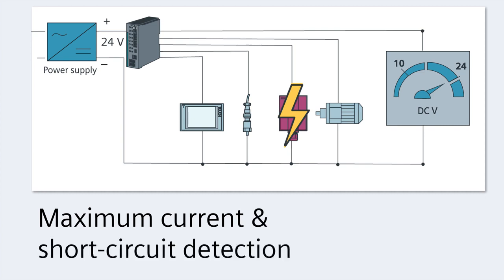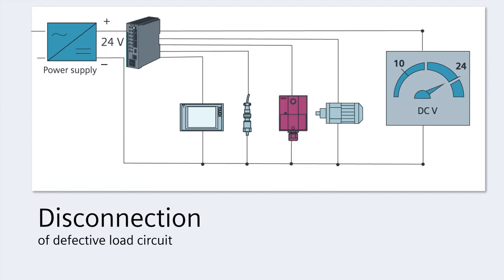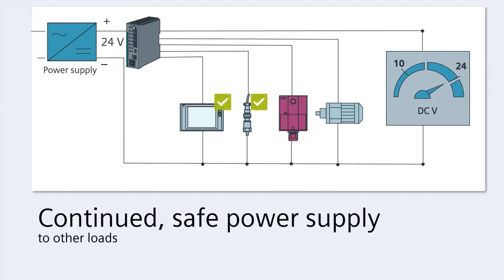In the event of a short circuit, the benefits are clear. The SEL1200 immediately detects the short circuit and disconnects the defective load circuit. Power continues to flow to the other loads without a voltage dip. This prevents a total plant shutdown.